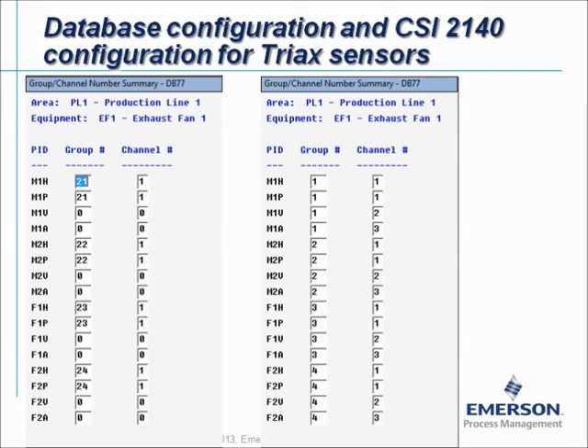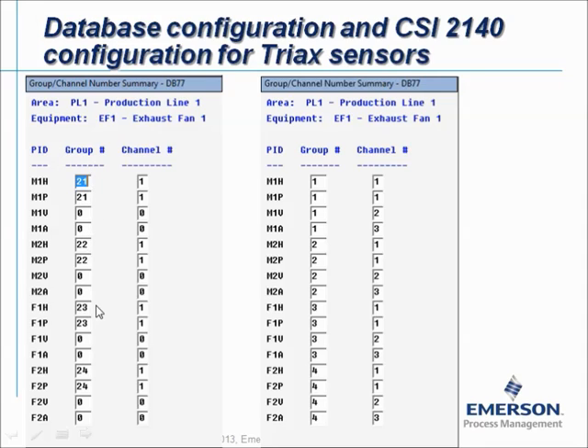If you go in the software to database setup management, you can go to a screen called group channel number summary. If you have built a machine with the database wizard, you will see automatically something similar to this — the horizontal and PeakVue measurements are in the same group so they will be measured simultaneously. Motor outboard, motor inboard, fan inboard, and fan outboard will always use channel number 1, the horizontal radial measurement.